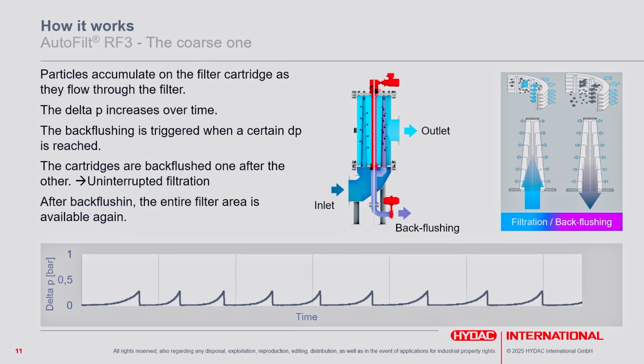We have the inlet at the bottom left of the filter and the outlet at the top right. Water with particles comes in at the inlet, and in the best case leaves clean at the top right outlet. As with every backflushing filter, there's a backflushing line with a backflushing valve and a backflushing device—in this case, the backflushing arm under each filter element, each candle, connected via the shaft to the gear motor.